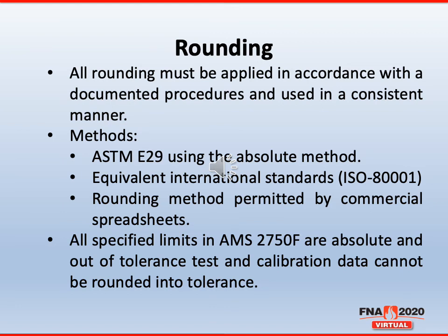All specified limits in AMS 2750 are absolute, and out of tolerance test or calibration data cannot be rounded into tolerance. For instance, if you do have a survey that you're shooting for plus or minus 10 and it reads plus 10.4, you are not allowed to round that into compliance.